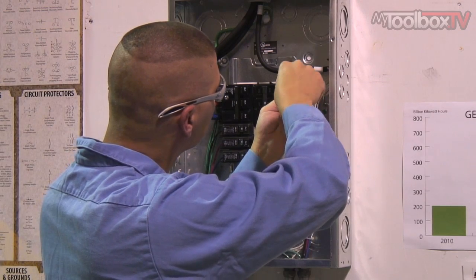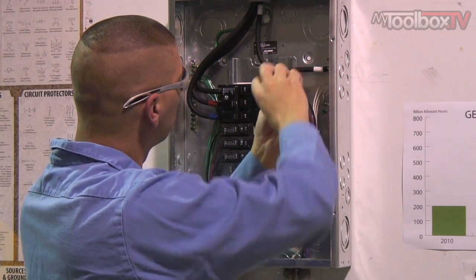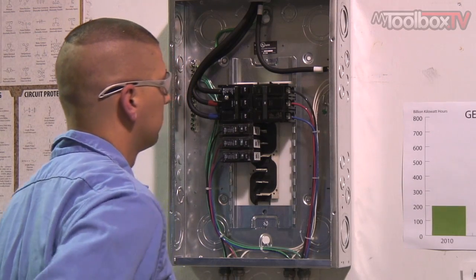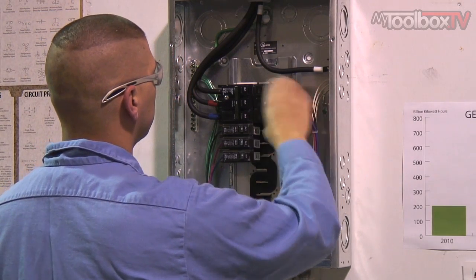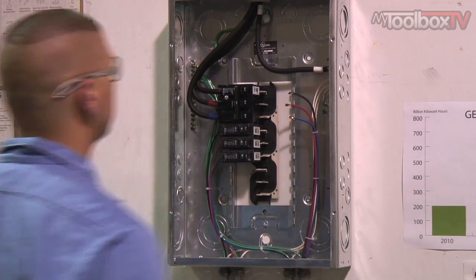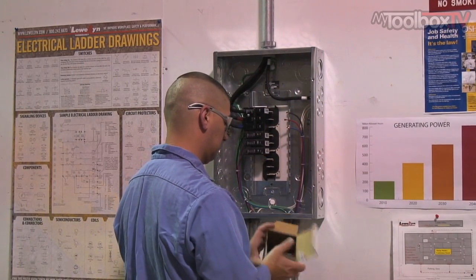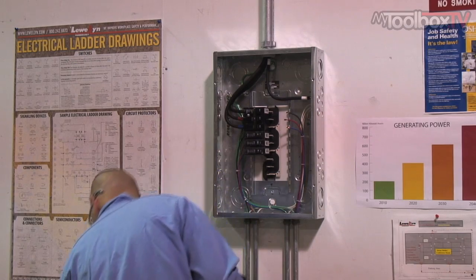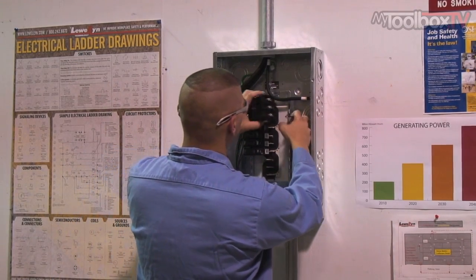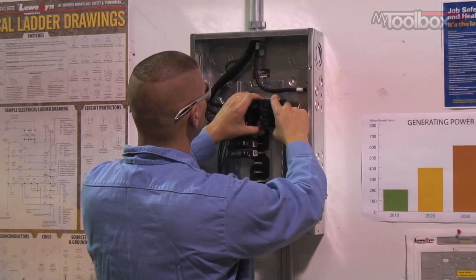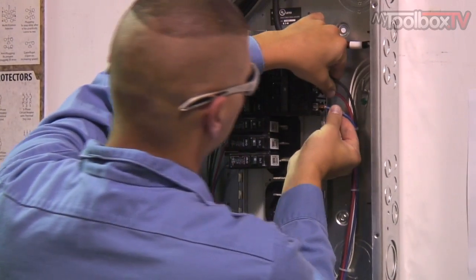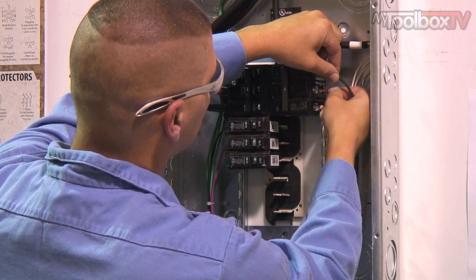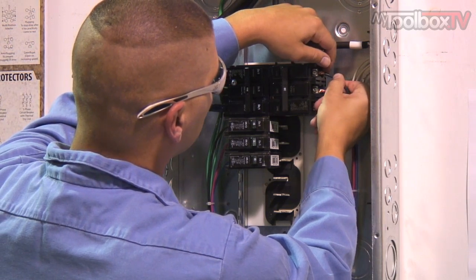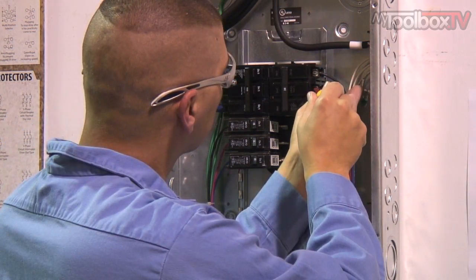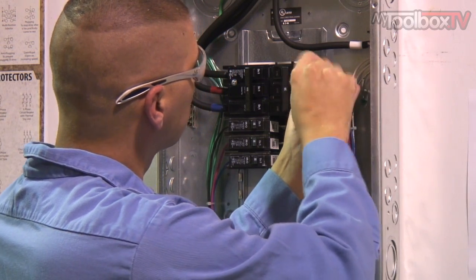You notice that he was not wearing PPE, but he was standing outside the zone, outside the arc flash boundary, so it was safe in what he was doing. Now he can determine that this panel is off, is isolated, and safe to work. And now the work actually begins, and he can take off the PPE for the arc flash hazard and the voltage protection. He leaves his safety glasses on just as a precaution, and the work occurs very quickly, and he is able to replace the circuit breaker, do it all de-energized as it should be, unless it can be justified, and that's hard to do.